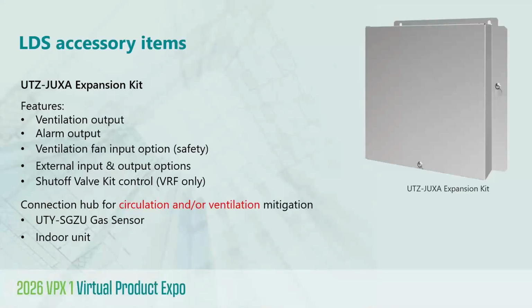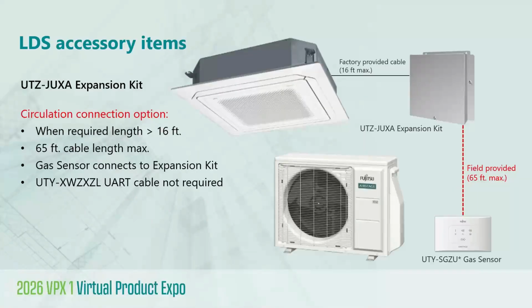Now, the kit also provides some additional outputs, including connections for an optional third-party alarm and shutoff valve kit. However, shutoff valve kits, if you're familiar with those, are used exclusively for our AIRSTAGE VRF systems and not H-Series. However, it's the exact same hardware. It's the same expansion kit that's used in both product lines. So with that overview in mind, let's return back to circulation and see how the expansion kit can help address gas sensor distance requirements that go beyond 16 feet.